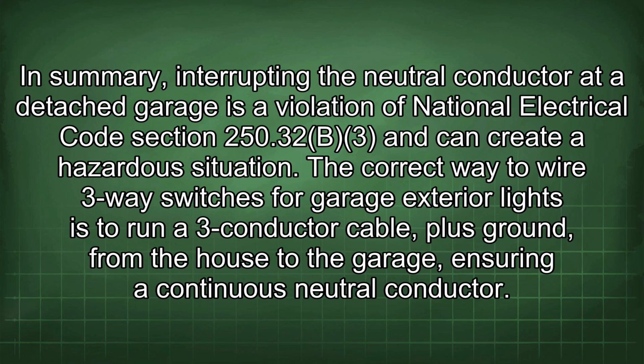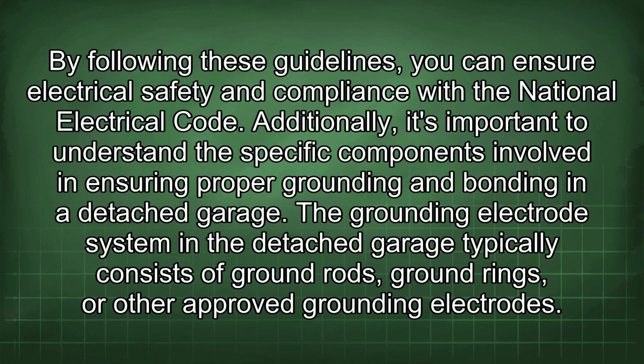In summary, interrupting the neutral conductor at a detached garage is a violation of National Electrical Code Section 250.32(B)(3) and can create a hazardous situation. The correct way to wire 3-way switches for garage exterior lights is to run a 3-conductor cable plus ground from the house to the garage, ensuring a continuous neutral conductor. By following these guidelines, you can ensure electrical safety and compliance with the National Electrical Code.